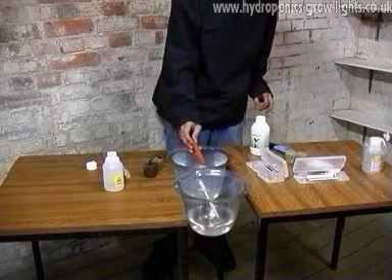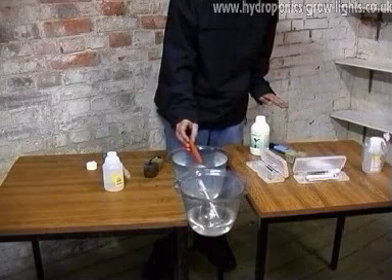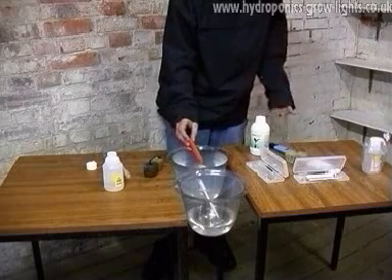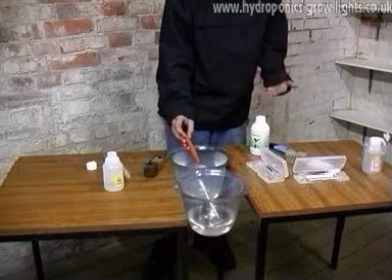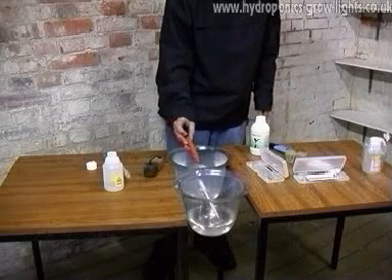And when you use them, it's a good idea to give them about 5 seconds in order to give a proper reading, because it can fluctuate because of the temperature of the water it has to compensate for. And that's a pH meter.